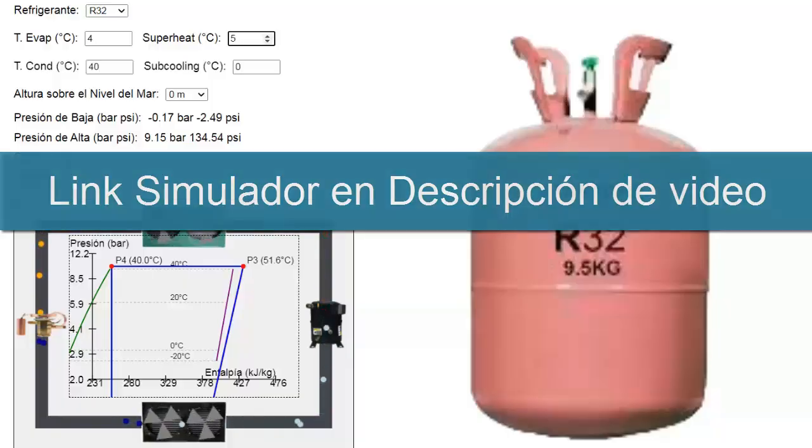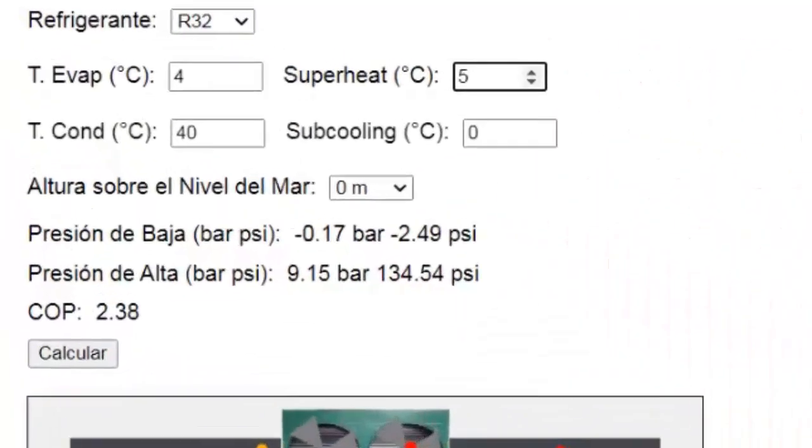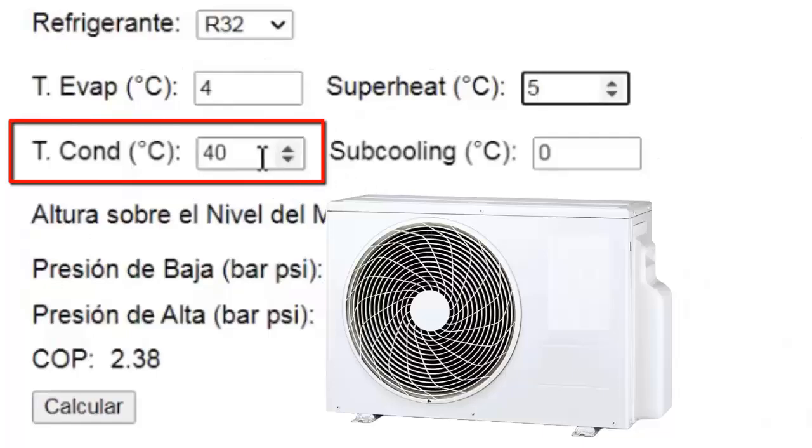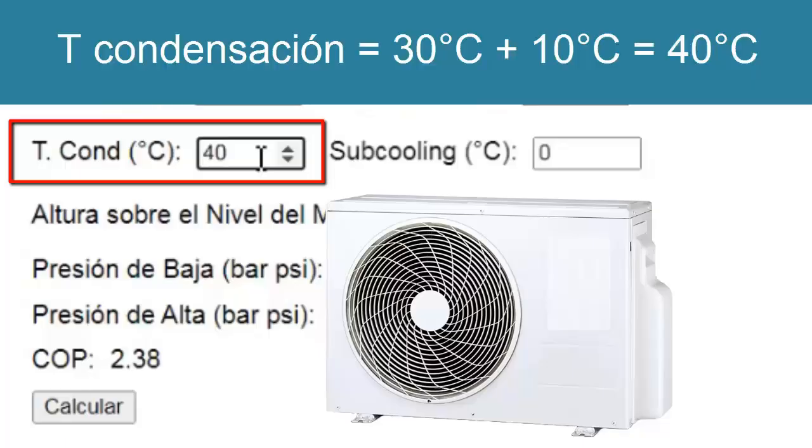Now let's focus on the condensation temperature inside the air conditioning system. To do this, we will add 10 degrees Celsius to the ambient outdoor temperature of the unit. For example, if the outdoor temperature is 30 degrees Celsius, the condensation temperature will be 40 degrees Celsius. By the way, the link to access this simulator is provided in the video description.